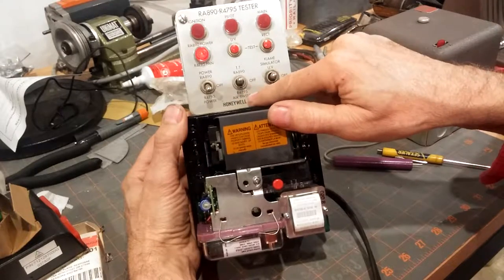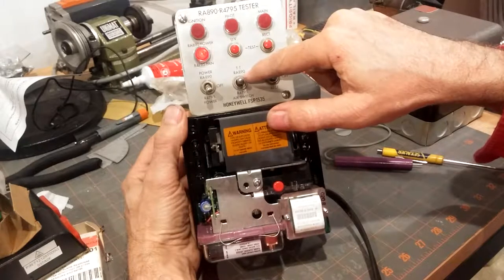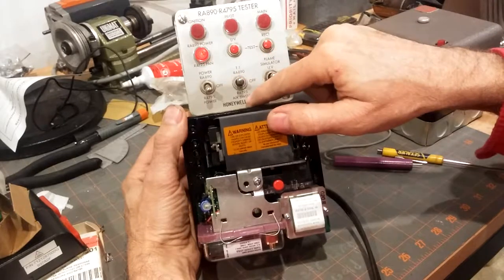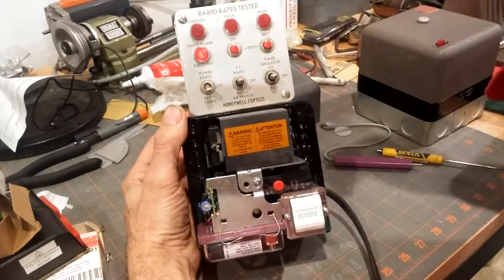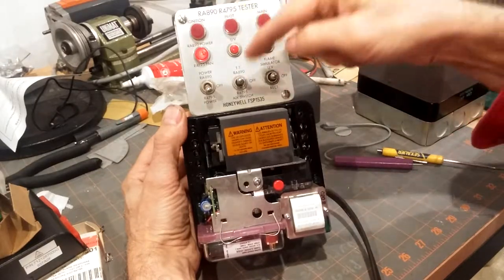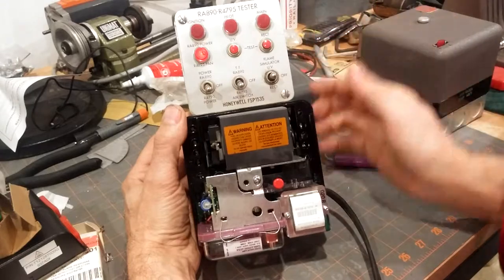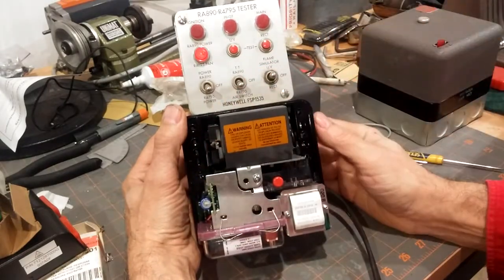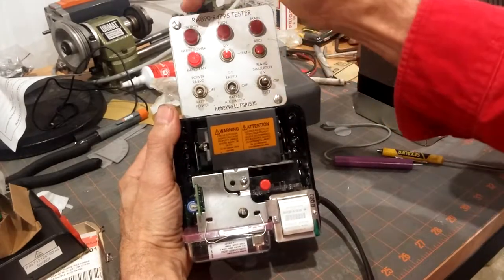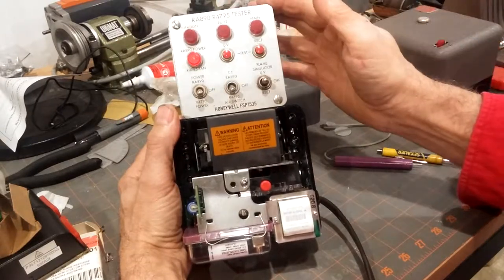If we flip it up, that would be for the RA890 control — we're assuming there's a call for heat. We're assuming that there's power, the fan is running, and now the air switch must be proven and pull in. Nothing's going to happen for 30 seconds because we've put in a purge card for 30 seconds. At the end of the 30 seconds, pre-purge, the trial for ignition begins, and the pilot light should energize showing that there is an attempt for ignition.